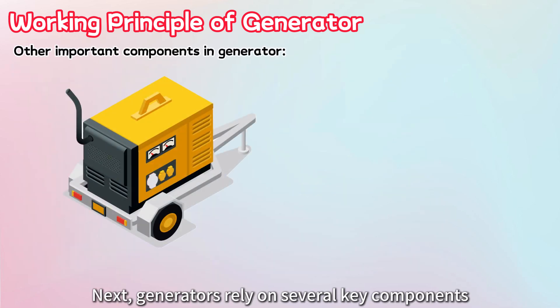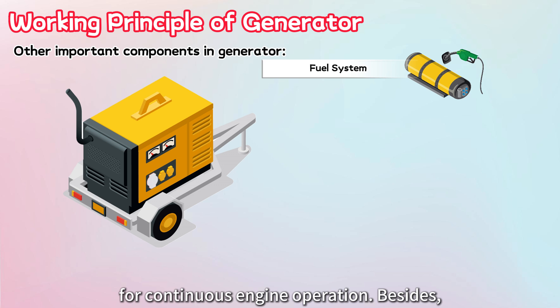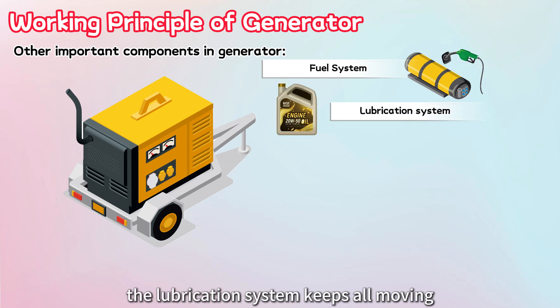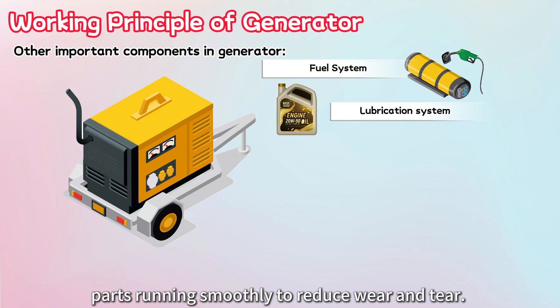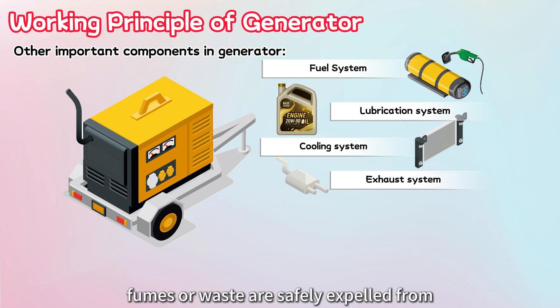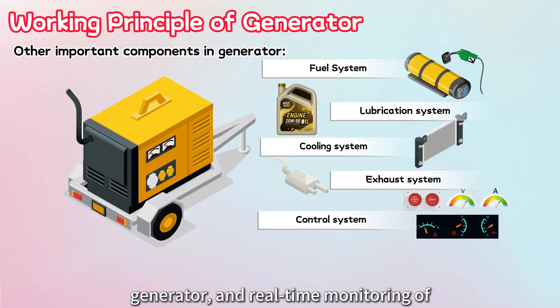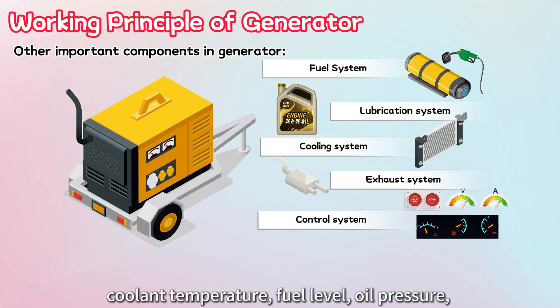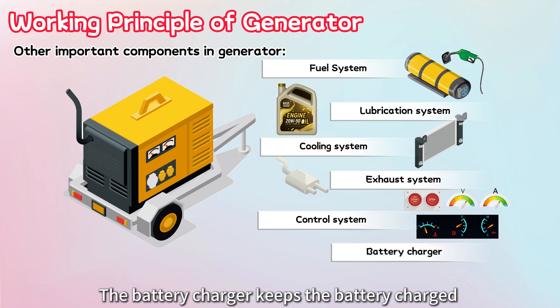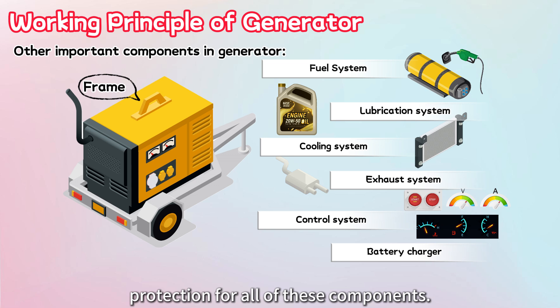Generators rely on several key components to ensure smooth and efficient operation. The fuel system supplies the fuel needed for continuous engine operation. The lubrication system keeps all moving parts running smoothly to reduce wear and tear. To prevent overheating, the cooling system circulates coolant and provides essential ventilation. The exhaust system ensures that combustion fumes are safely expelled. The control panel allows us to start or stop the generator and monitor parameters such as voltage, current, coolant temperature, fuel level, oil pressure, and rotational speed. The battery charger keeps the battery charged and ready for use, and the frame provides structural support and protection for all components.